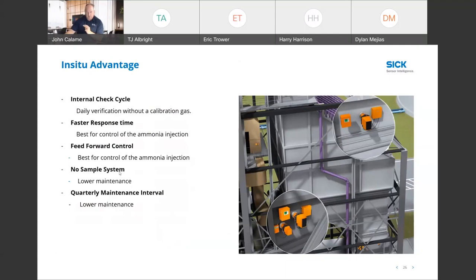You still have to use your gas for your quarterly checks. So we can still introduce gas to the device, and you'll see that coming up a little later how that's accomplished. But we can do both live gas as well as mechanically online without removing the analyzer via a mechanical device, filters and things. You'll see that just in a minute.